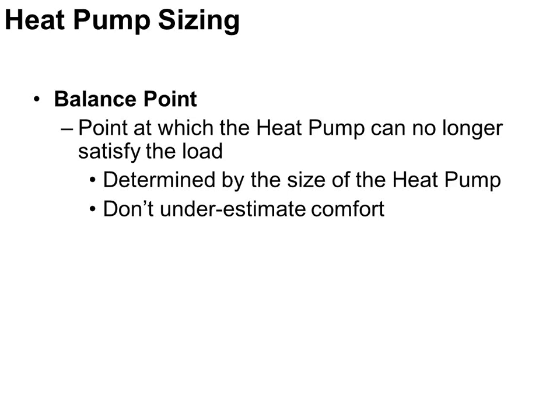Right? So what happens on a heat pump is I end up traditionally sizing the heat pump for the cooling load, and then when it goes into heating mode, I just kind of get what I get, and then when the temperature drops off, I don't get as much. All right? So traditionally, we would size a heat pump for the air conditioning load, and we typically would round down a little bit. So if I had a load of 38,000 BTUs, I would put in a 36,000 BTU 3-ton air conditioner, and that's what I would do, right?